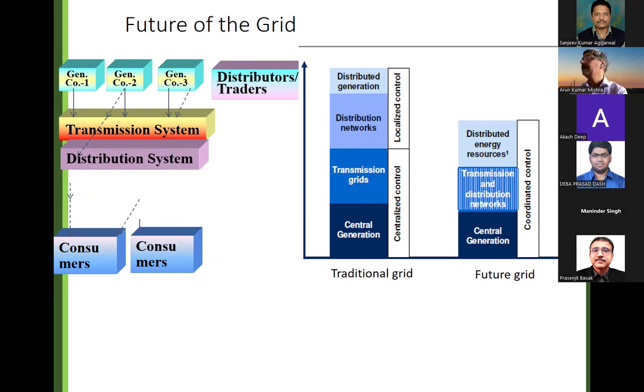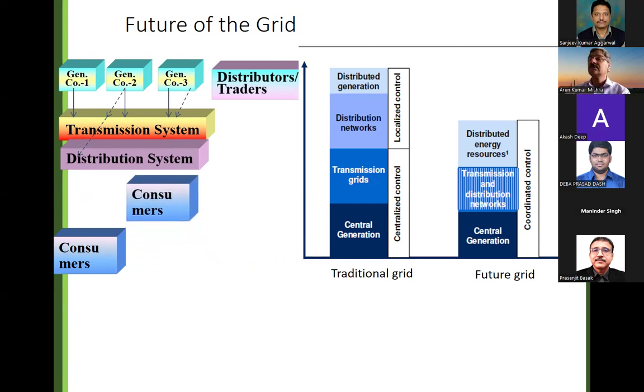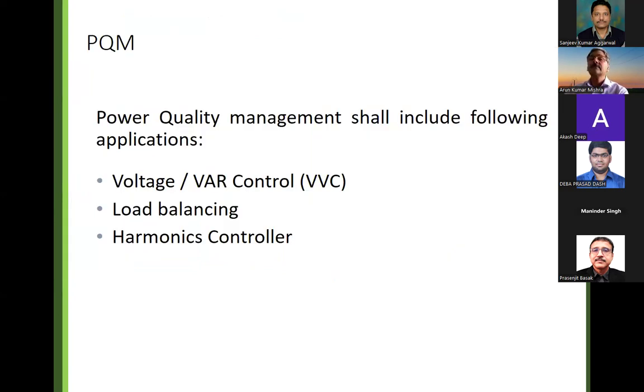The next slide is about power quality, which is basically three things: voltage and VAR, load-generation balance meaning frequency, and harmonic control. Having laid out the overall system, this is the quality where power system operation control has to focus. Voltage and overall VAR consumption, load balancing, and frequency have to be maintained. For a change in our country, the frequency range is currently 49.95 to 50.05. Earlier the band was much larger, because we are slowly getting more disciplined and building adequate resources. As late as 2020, the grid code said we should go for free governor mode of operation. Then, of course, harmonic controls.